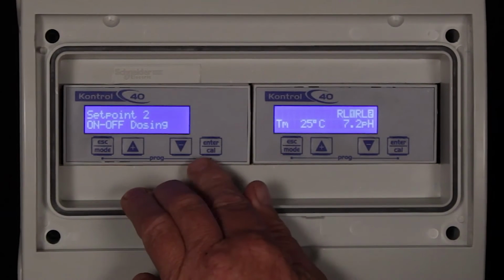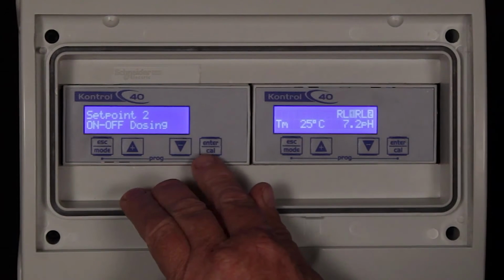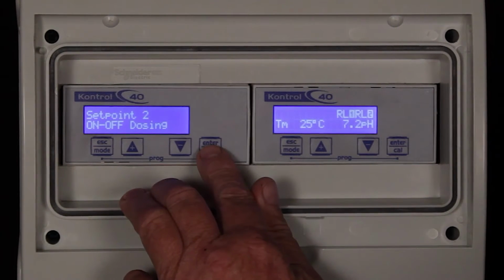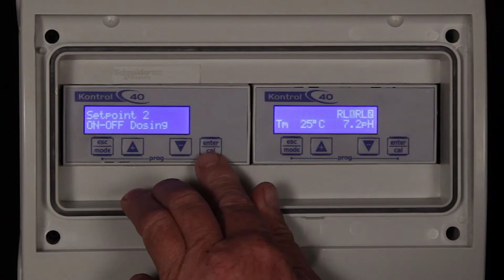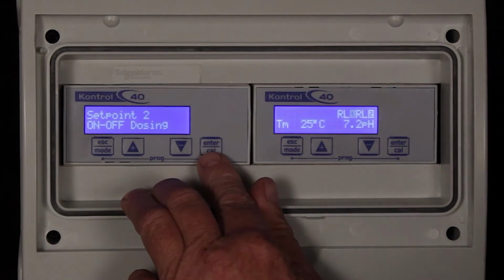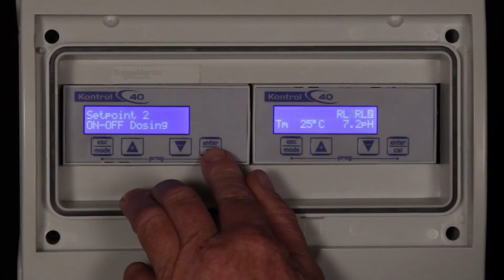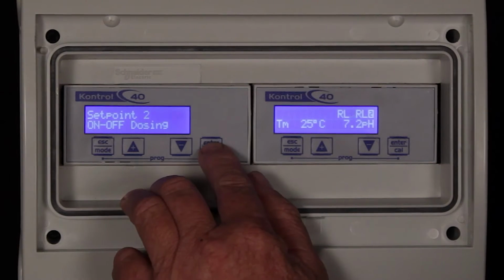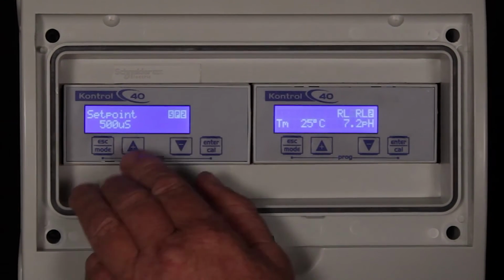Set point 2 is used for our interlock with the pH controller and pH pump. Please take note, the values in set point 2 must be the same as in set point 1 for the lockout of the pH system to work correctly. So if you change set point 1, you have to change set point 2 as well.